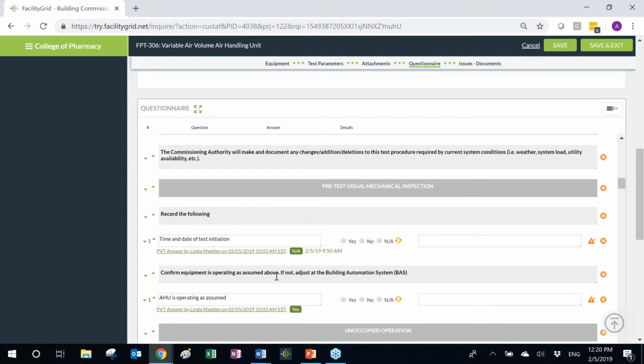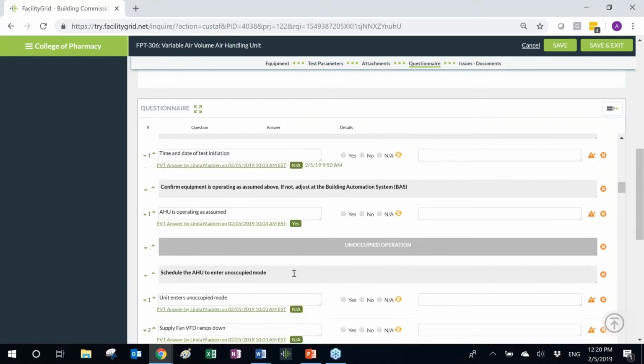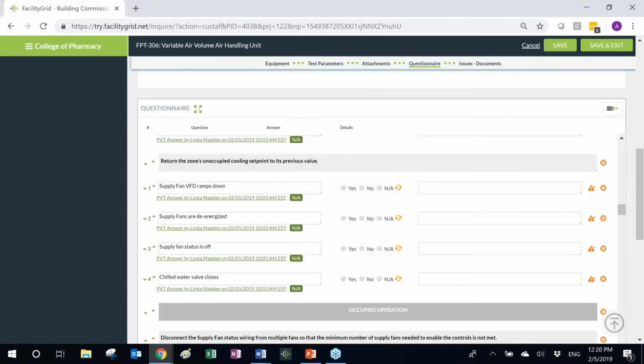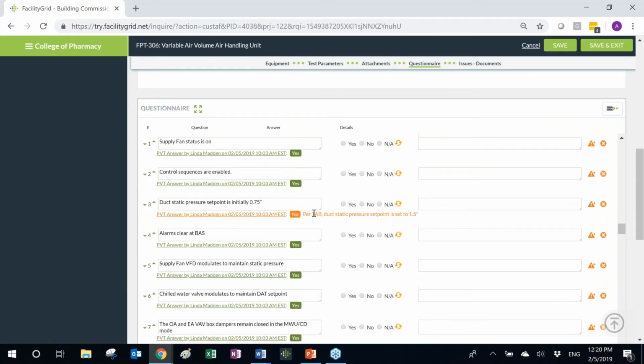So if by the time I'm looking at this FPT, I have addressed the issue that was brought up by the controls contractor, and I've already modified the functional testing procedure, this question, and I deleted these questions because in this case, they no longer make sense because there's no unoccupied mode of operation. So these questions would not even be part of my FPT. Also, as I scroll down, I'm going to get to the information related to the static pressure set point, where the contractor indicated that the set point is actually 1.5, not 0.75.